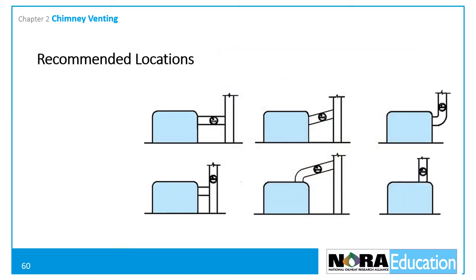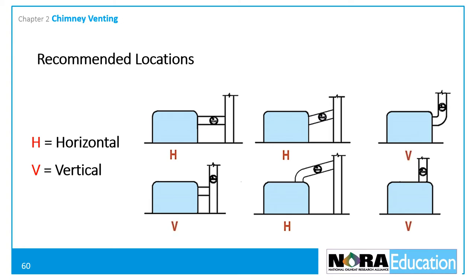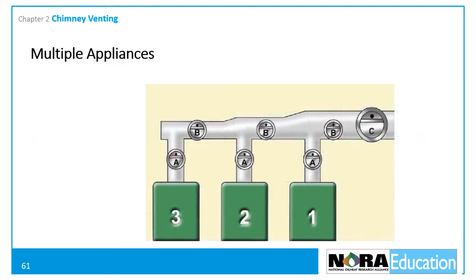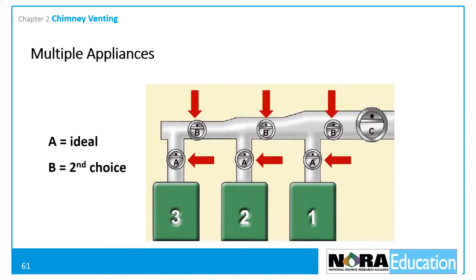This diagram helps an installer or technician determine if a location is considered horizontal or vertical, with H's indicating horizontal positioning and V's indicating vertical. When several appliances are vented into a common chimney connector, each should have its own draft control in position A — the uptake between the appliance and the main breeching. If the uptake is too short, locate the control in position B, the main breeching. If neither location is possible, install a single large control in location C between the chimney and the nearest appliance.